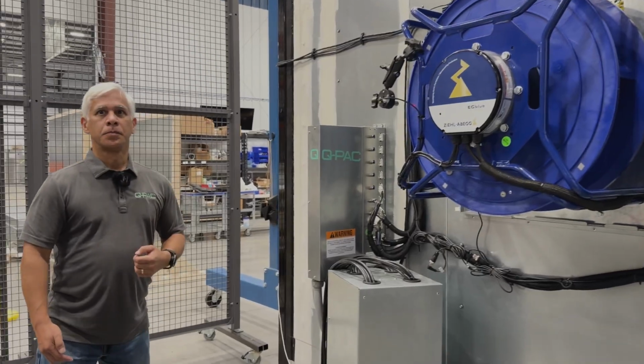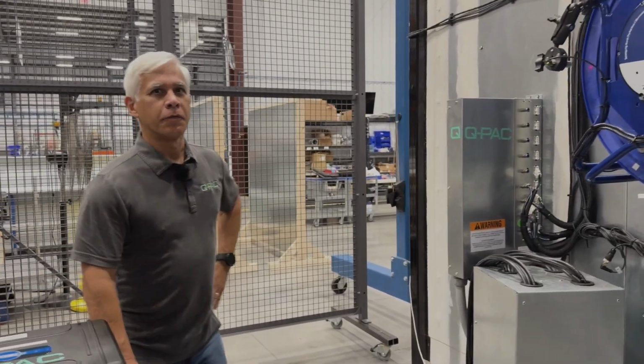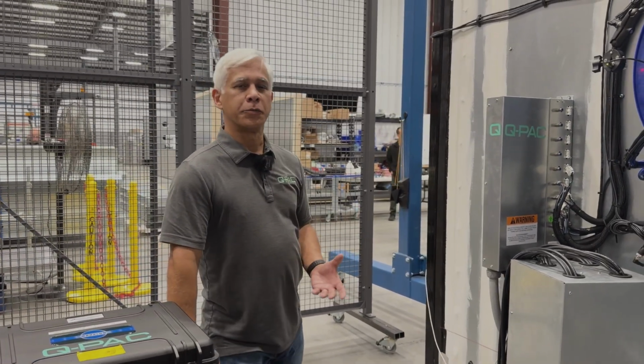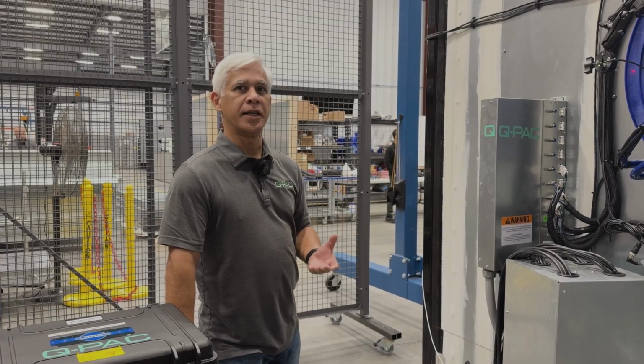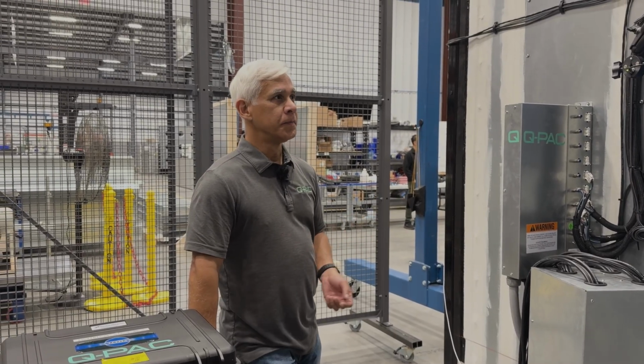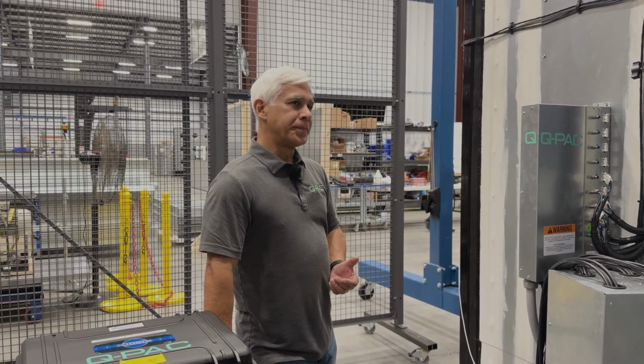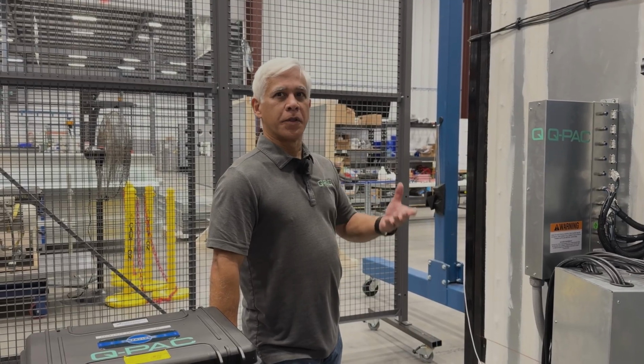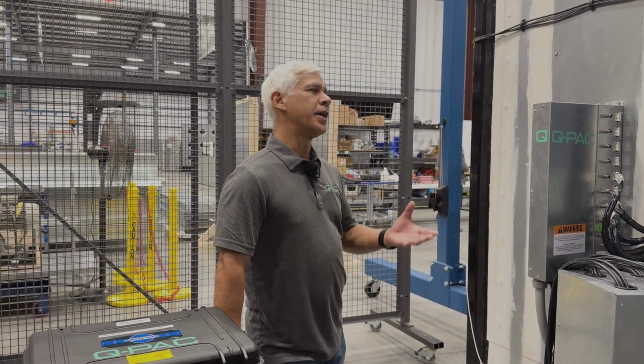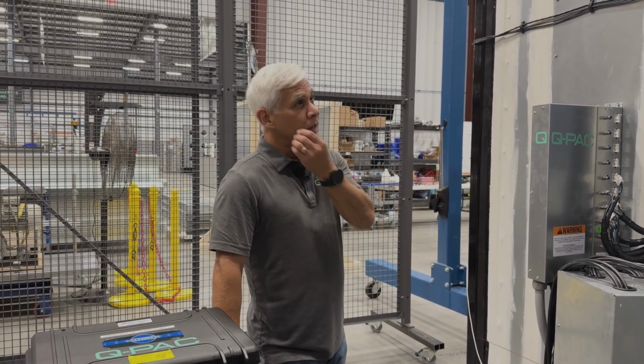What are you expecting to be the impacts of that voltage on the fans? Well, of course we know that as we lower the voltage, in order to maintain the same amount of power, we have to raise the current. The more current you have, the more heat loss you have through the wiring. So we know that's an important factor.